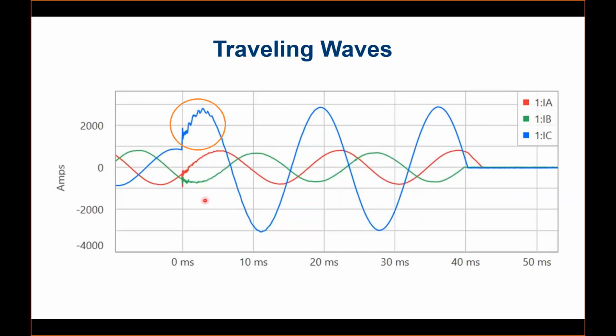And the phasor-based technologies, which are based on sampling the data at a slow rate, are not able to catch these very high frequency transients. So this is one of the principles that differentiates the conventional phasor-based technologies from traveling waves. We decode the information, or the trend, that we get from this region and make the decision very, very fast.